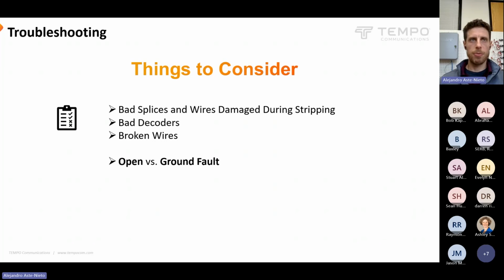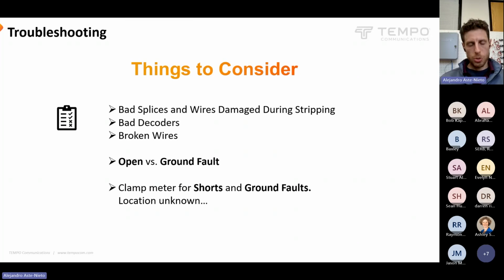You might have an overcurrent right after it rains. Meanwhile, you have decoders offline when it's in drier weather, and that's just because there's a wire exposed and it's making electrical contact when there's water, and it's just adding resistance when there's not. So when there's a short or a ground fault, there's some kind of high current going on. Your controller is not always going to be so helpful in giving you clues as to where that is. So a clamp meter is going to be most helpful in those situations.